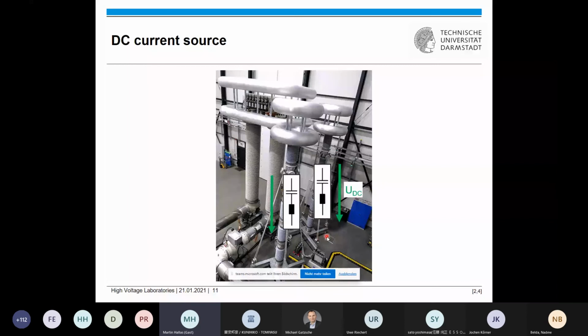And on the other side, you know that capacitors have a lower impedance when you increase the frequency, and this you can use when you put an AC-AC converter on earth potential, which generates a high frequency current. We are using frequencies in the range of 50 kilohertz, and this high frequency current can be transmitted through the capacitive loop. This transmission can be performed as a serial resonance circuit when you also add some inductances in this, and the resonance frequency of this can be adjusted with the AC-AC converter at earth potential.